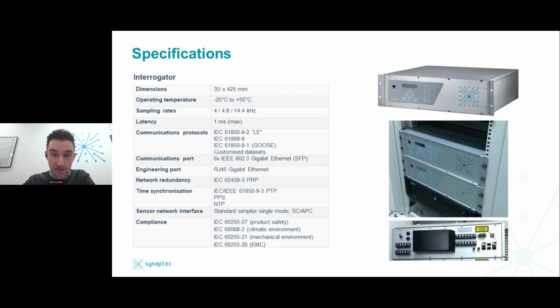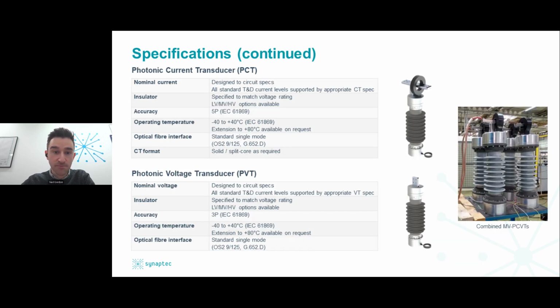So here you can see what the interrogator looks like in practice. This is a 3U rack mountable device capable of sampling at up to 14.4 kilohertz as standard. It's compatible with IEC 61850-9-2 and GOOSE outputs as well. And importantly for a device like this, it is type tested to the same standards as protection relays for substation environments. So that means IEC 60255 and 60068. And just moving on to the sensors as well.